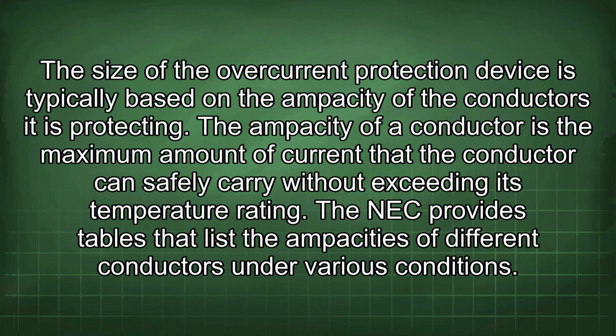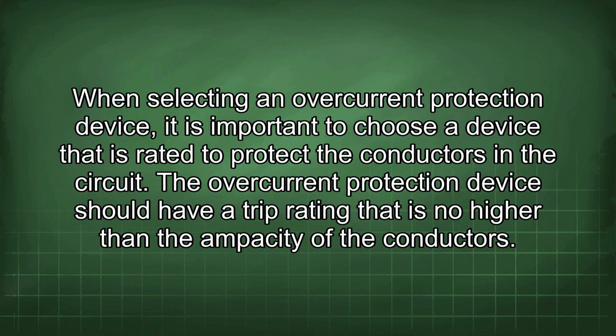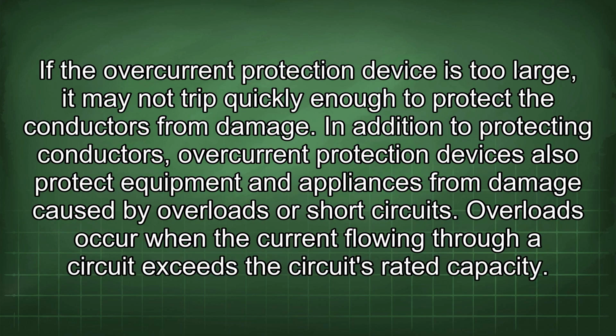The NEC provides tables that list the ampacities of different conductors under various conditions. When selecting an overcurrent protection device, it is important to choose a device that is rated to protect the conductors in the circuit. The overcurrent protection device should have a trip rating that is no higher than the ampacity of the conductors.